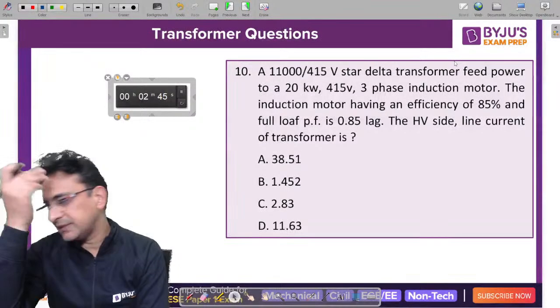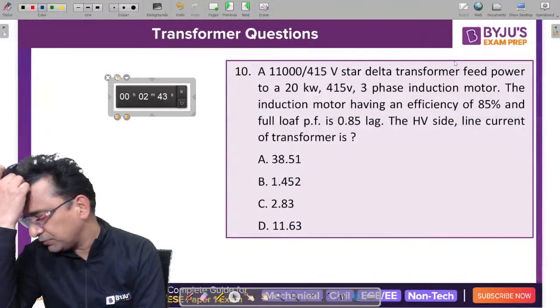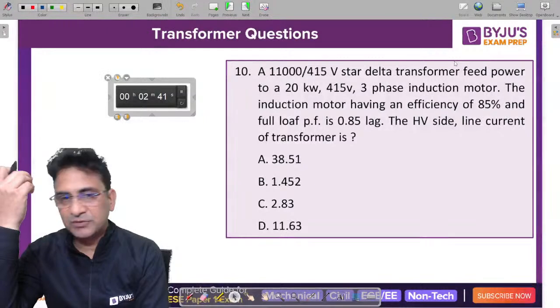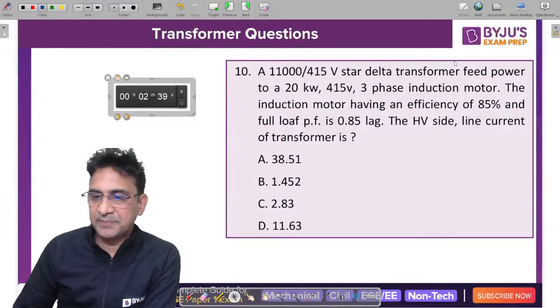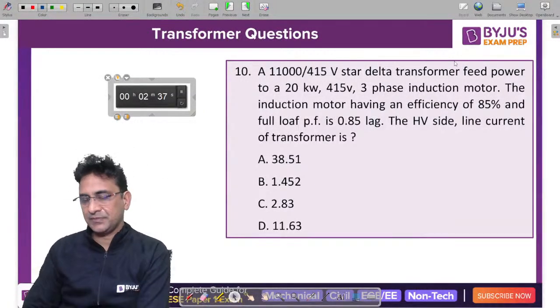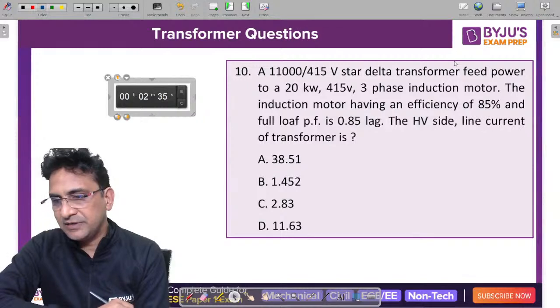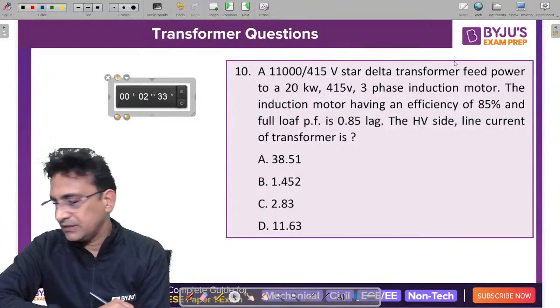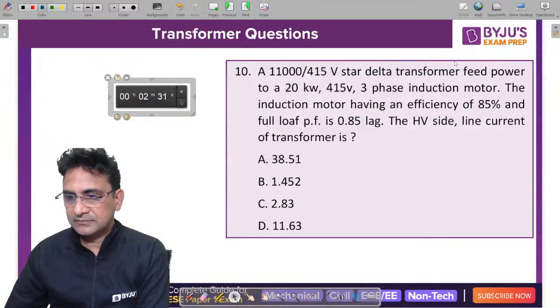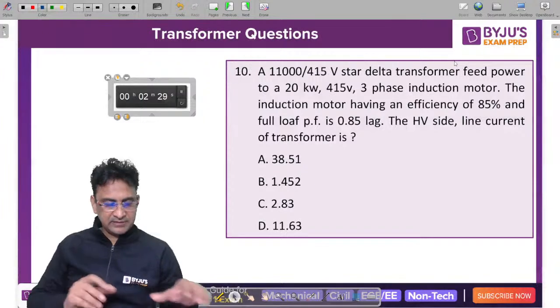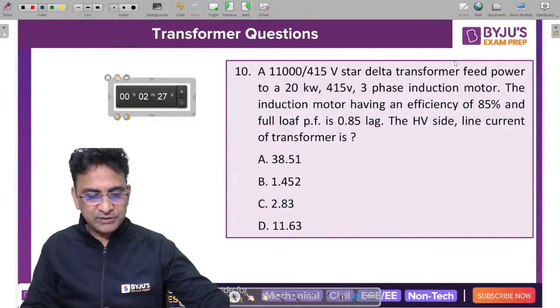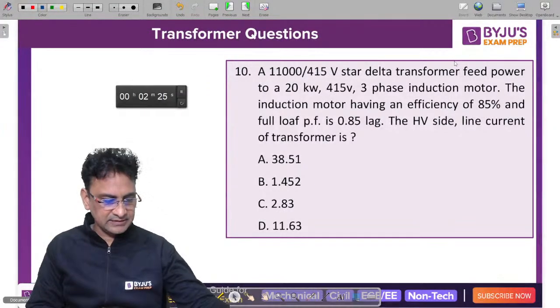Both are at the same point, but the current is flowing due to the transformer action, because the transformer action is taking place between the primary winding and the secondary winding. So I1 upon I2 is equivalent to N2 upon N1. So always remember, the circulating current flows both in the primary as well as in the secondary winding.